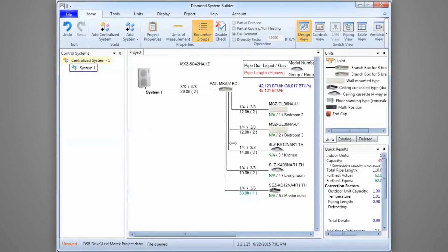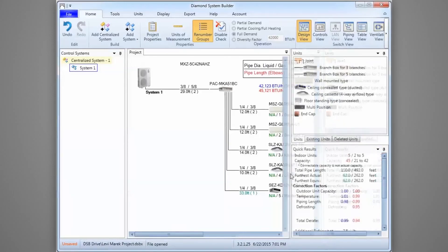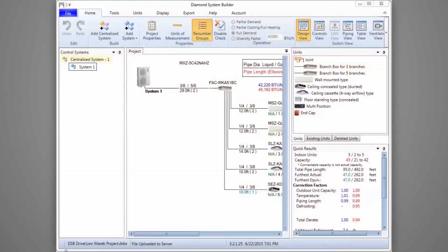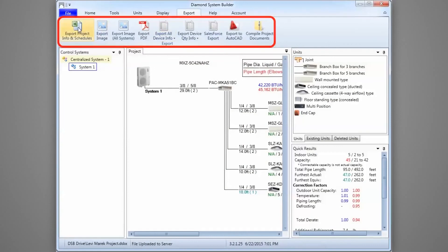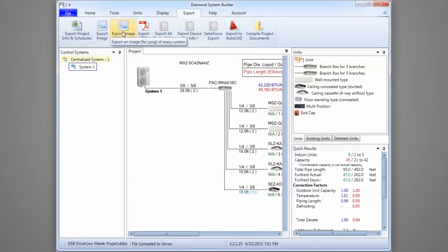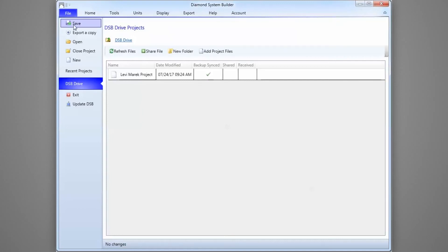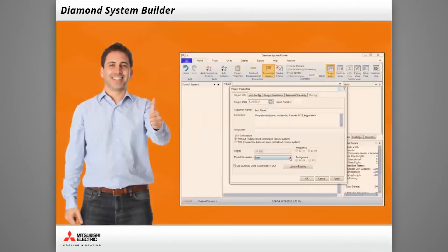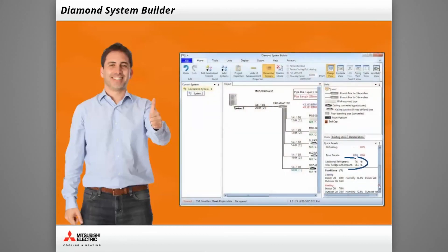The as-built design is now complete. Now we'll review the quick results to verify the necessary refrigerant charge. Our as-built system needs 7.6 pounds of added refrigerant, bringing the total refrigerant amount to 18.1 pounds. Completed projects can be exported for your business records — select the Export tab and review the various formats available. Before closing DSB, save the project. This concludes the Diamond System Builder tutorial. Entering design conditions and project properties ensures equipment compatibility and proper refrigerant charge.